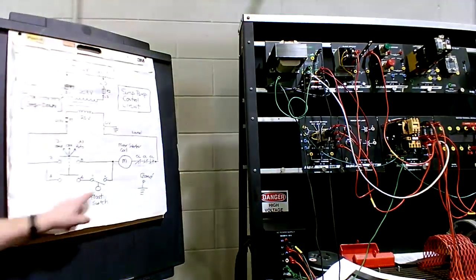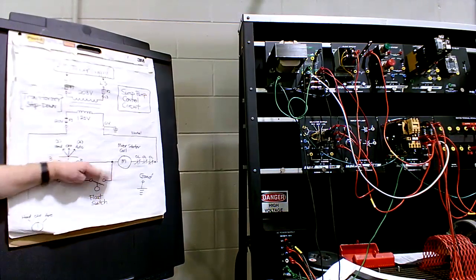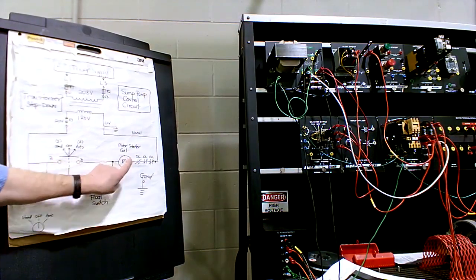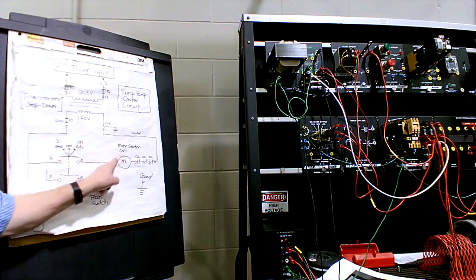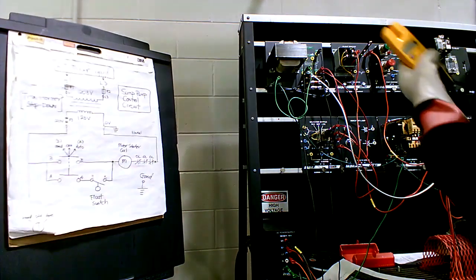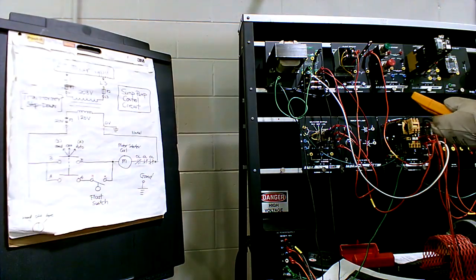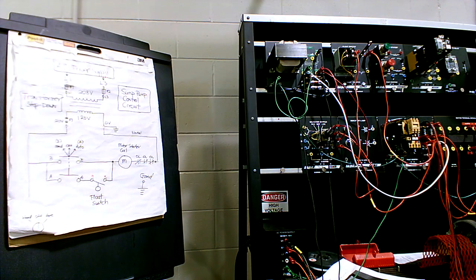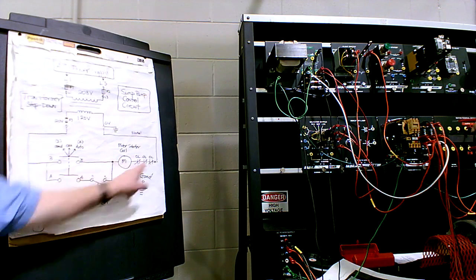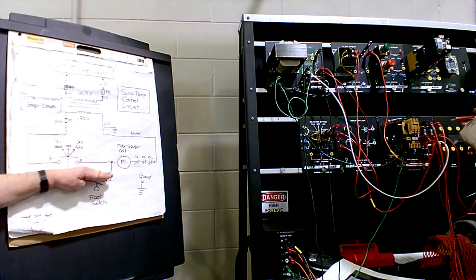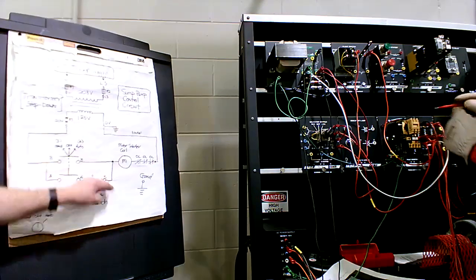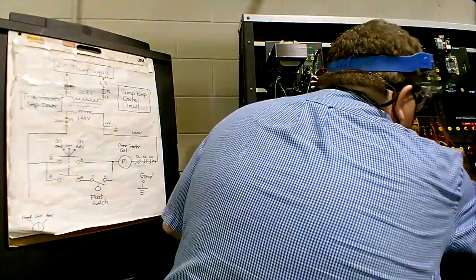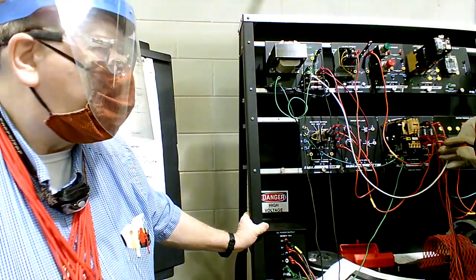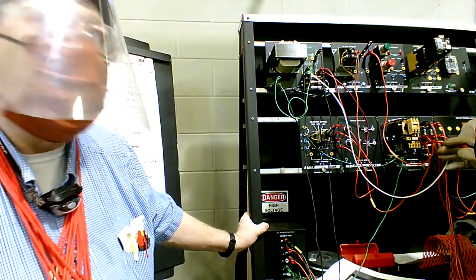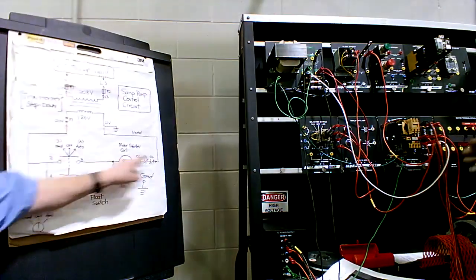So here, if you look, guys, the float is what actually gives you the control voltage. Put your meter across the coil there and tell me what you get voltage-wise. Roger, you hold the meter up there for him. He's going to check coil voltage with the float on, with the water up in the pit, across the coil, here and here. So what are you getting? He's got 120 volts across the coil.